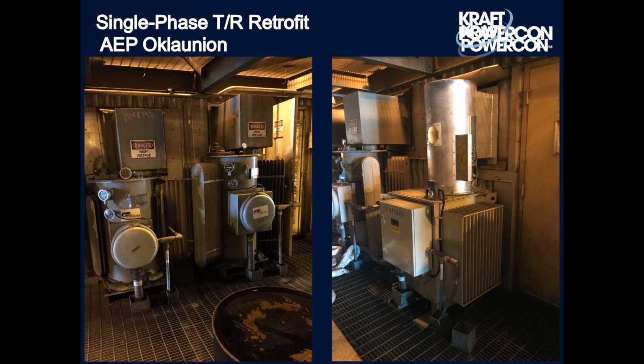Eventually, the oil that's on the inside of the transformer rectifier is now on the outside. Well, specification calls for the oil to be on the inside. So you've got a safety issue of leaking oil. You've got a potential failure there if the oil leaks too low, or you let that oil leak happen for too long. So now you've got an issue in the plant that you need to face. You have a round TR that hasn't been made in a number of years, connected to a rather odd bus duct system at the top.